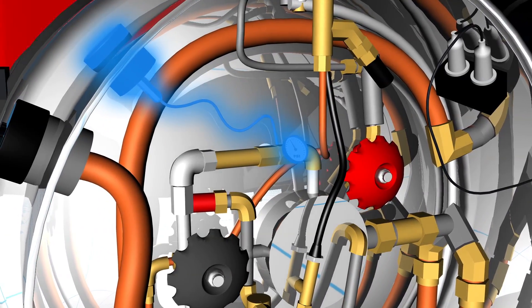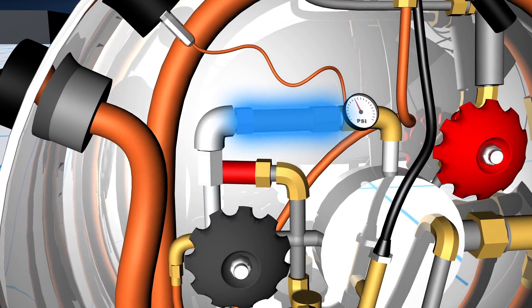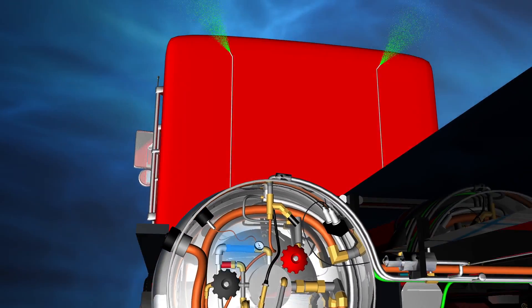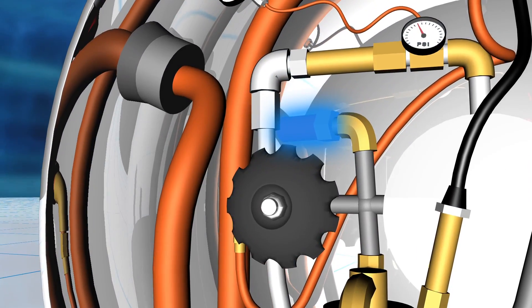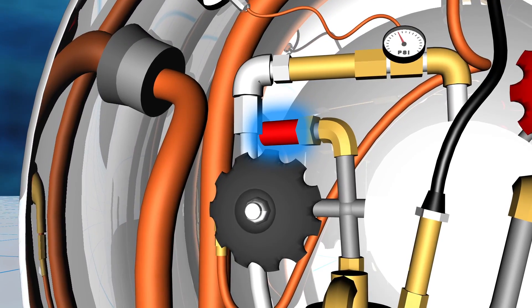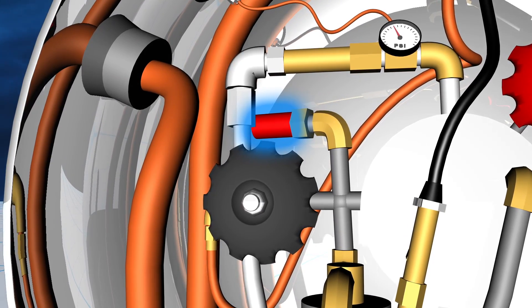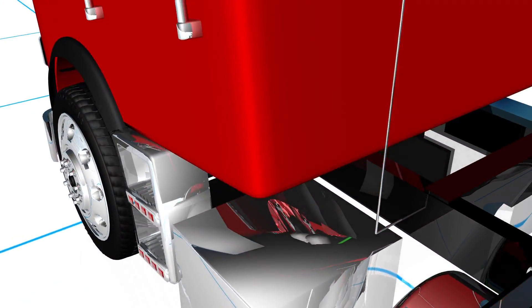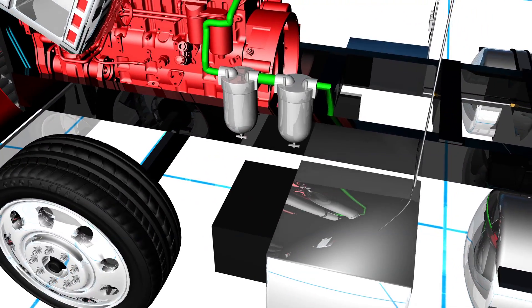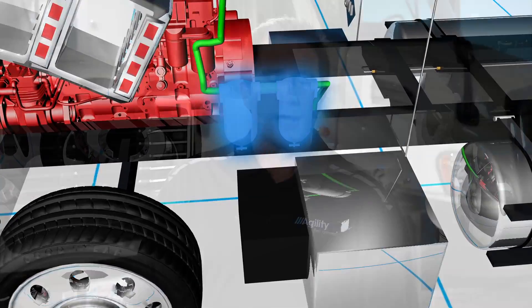The primary and secondary relief valves protect the tank from excess pressure. The primary valve activates at 230 psi and the escaping vapor is vented safely. The secondary valve is capped and activates at 350 psi. If you ever see the red secondary relief valve cap missing, you must consider the fuel system unsafe and take appropriate action as described in segment 7. Gas at between 100 and 150 psi leaves the overpressure regulator and goes to the engine low pressure filter. A hose from the low pressure filter routes gas to the engine, where an internal regulator further reduces the gas pressure.